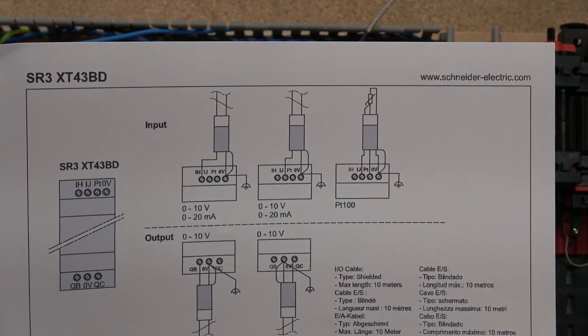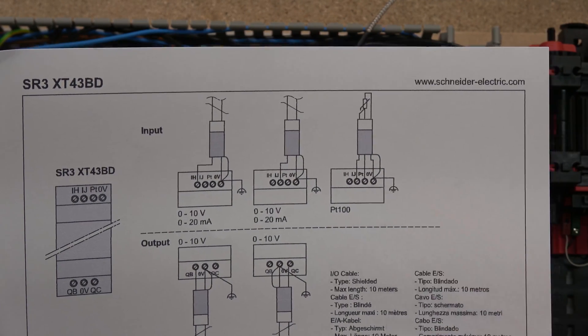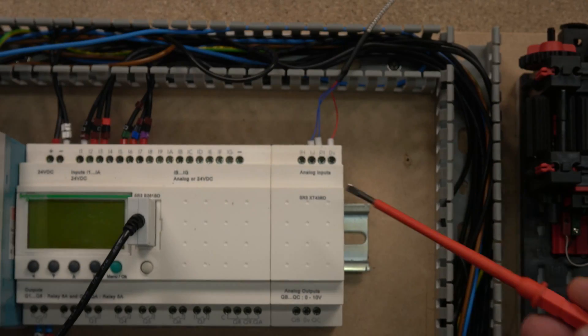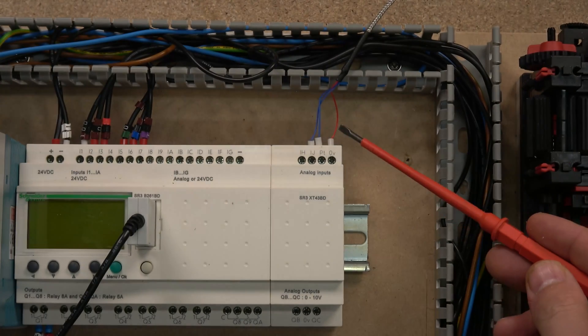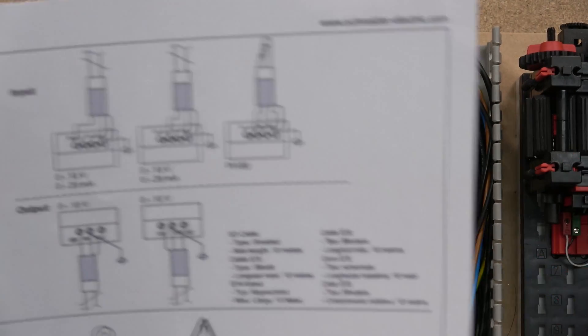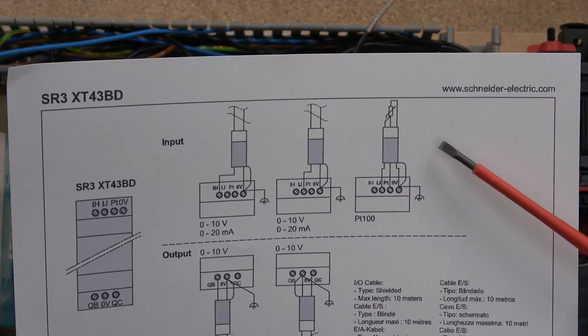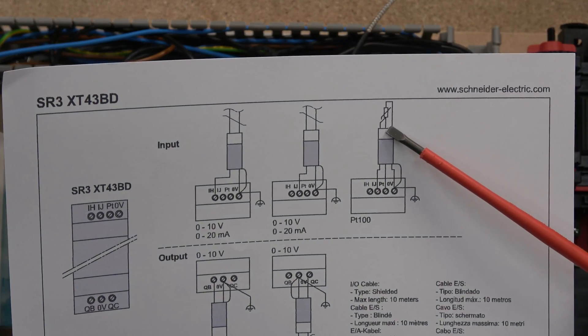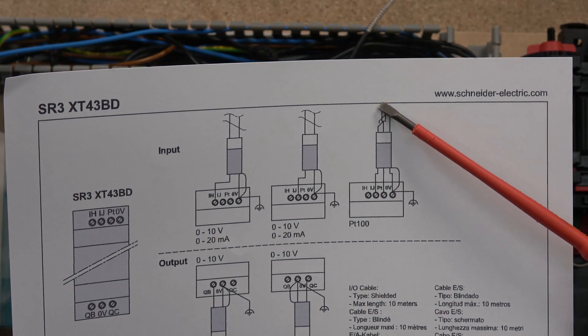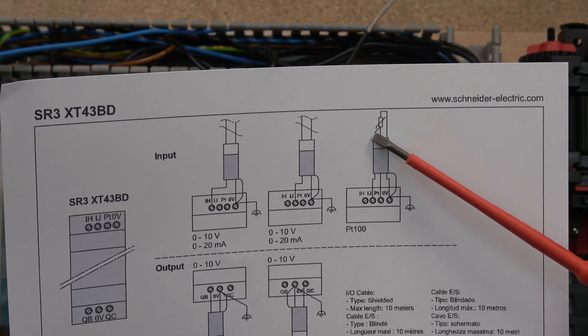As you can see for PT100, it is showing you in here how to wire it for the three wires. If you're trying to work it out, as you can see I've got two blues and one red. The best way I would work out which one is which is the single cable joining into one end and then the two joining up in the other end.